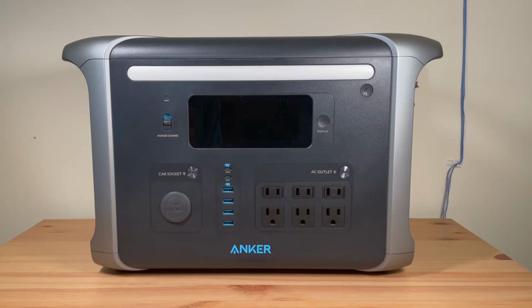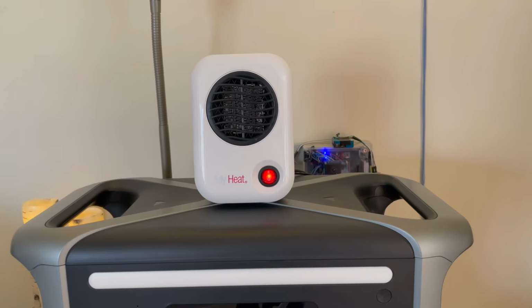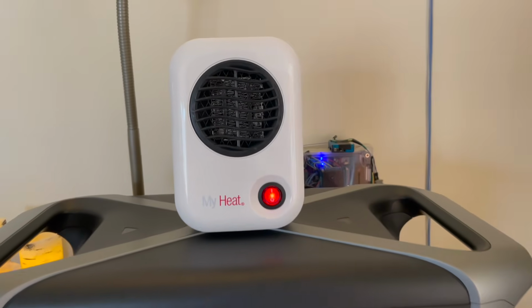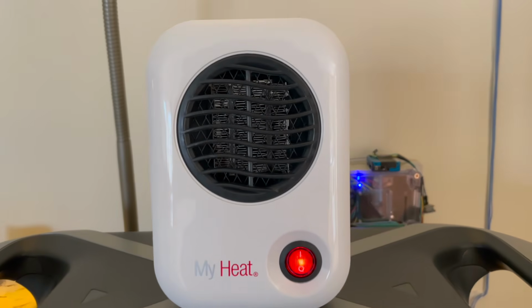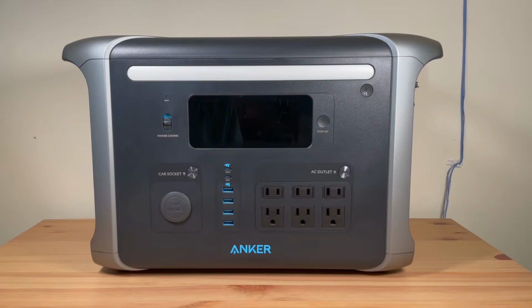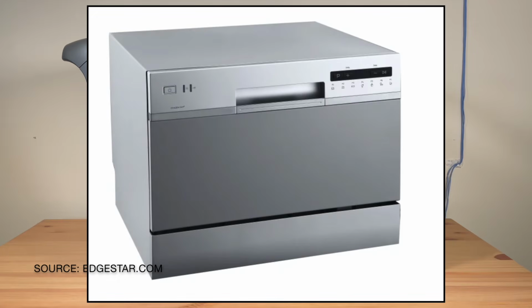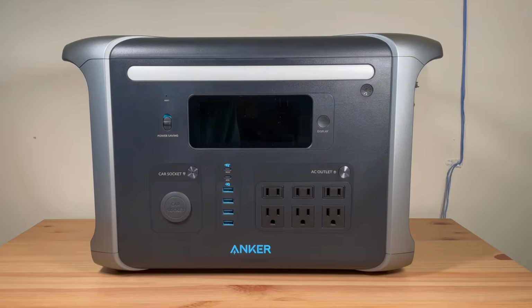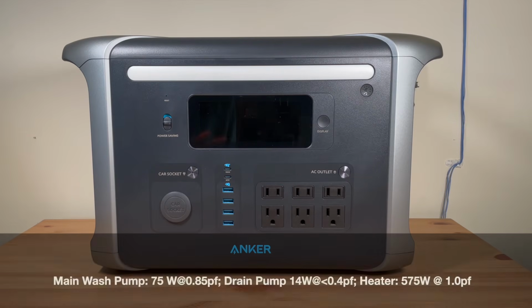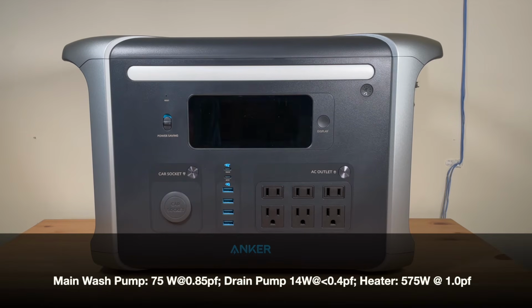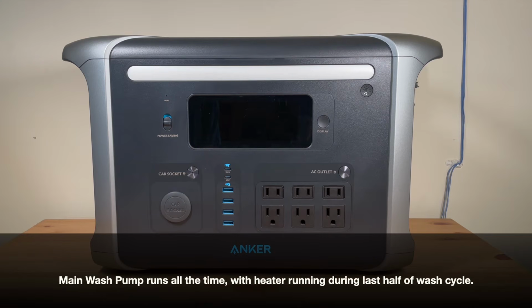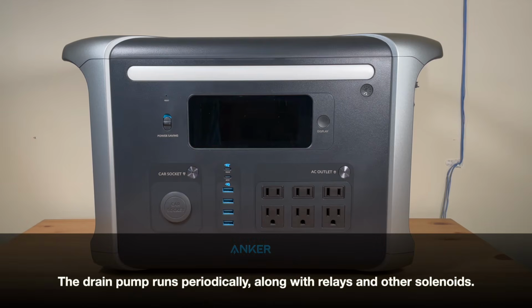So what I did was use two different loads as a representative set. One was a purely resistive load, a smaller one, about a 200 watt portable space heater, tested by itself. The other was a standard portable dishwasher. Starting with the dishwasher, that one has variable loads, a variety of different components: pumps, motors, a heating element to heat the water. It has resistive elements with high power factor, a motor with pretty good power factor, and solenoids, which have poor power factor.